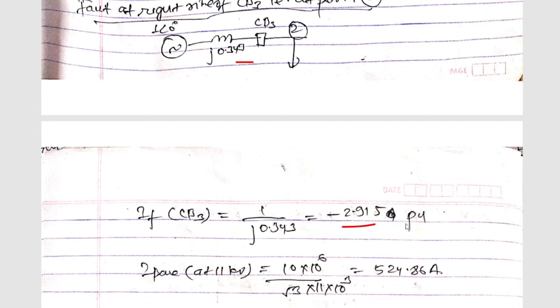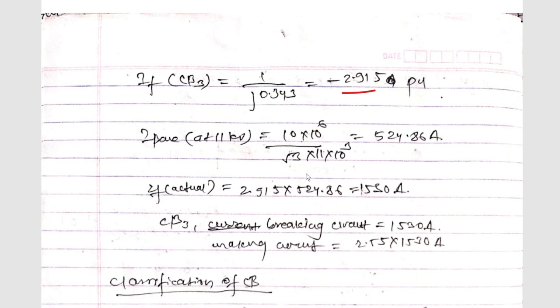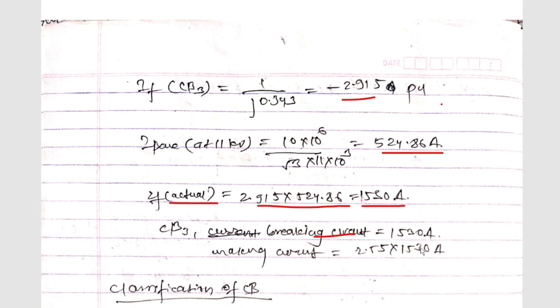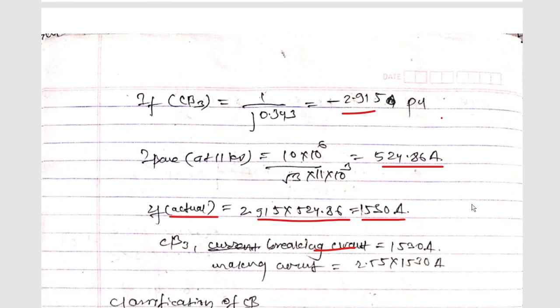With only G2 considered, the reactance is j0.343, so fault current = 1 / j0.343 = 2.915 per unit. Base current at 11 kV = 524.86 ampere. Actual fault current = 2.915 × 524.86 = 1530 ampere. Breaking current = 1530 ampere, and making current = 2.55 × 1530 ampere. In this way you can calculate such types of numericals. Hope you enjoy the lecture — thanks for watching and please don't forget to subscribe!